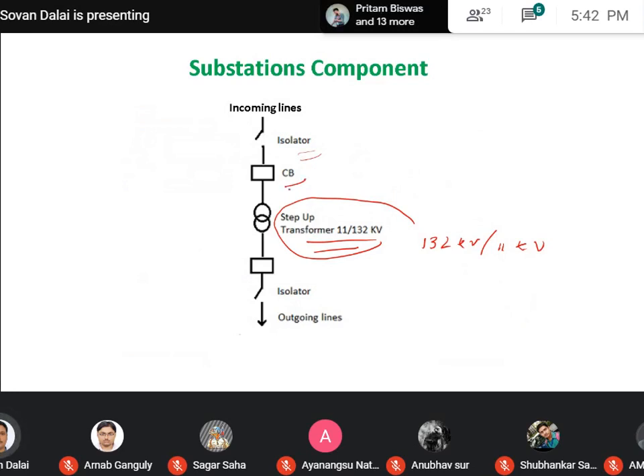An isolator is required, a circuit breaker is required, and here two things are not visible. One is the current transformer, which is required to measure the current, and another is the potential transformer, which is required for the measurement of the voltage. Okay. And this is connected to the consumer. So these are the components present inside a particular substation. The major component is obviously the transformer. Other components are the isolator, circuit breaker, current transformer, and potential transformer.